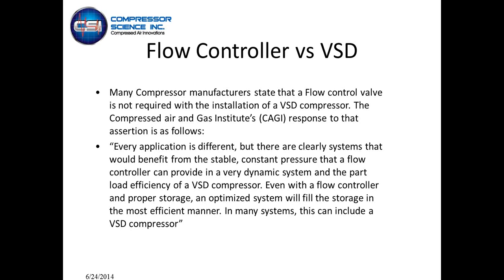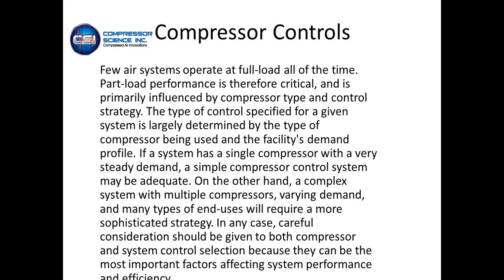to deal with those events out in the plant. Or there's such a large event in the plant that too much volume would have to be applied from storage to deal with that event, and this is where you have to look at the process side to see what's happening out there. Are we better off dedicating a compressor to that process, or dealing with storage out on the process side to deal with that specific event?